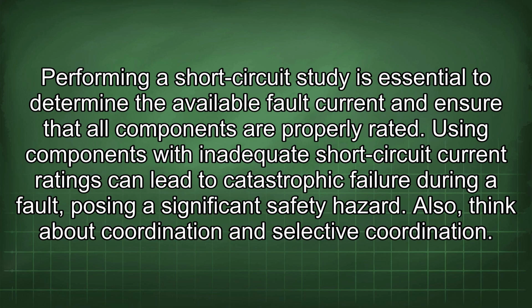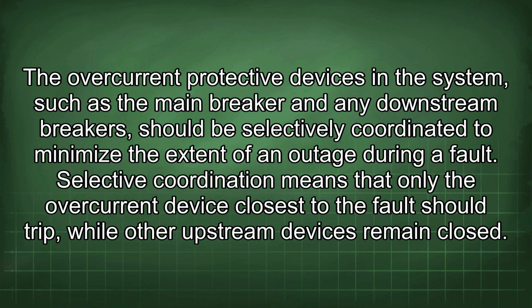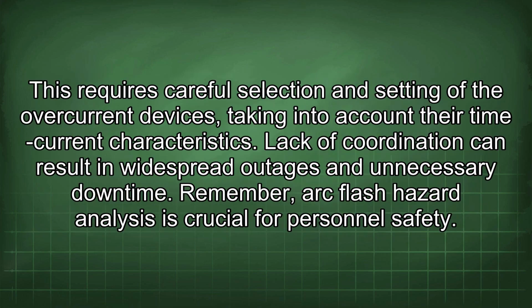safety hazard. Also, think about coordination and selective coordination. The overcurrent protective devices in the system, such as the main breaker and any downstream breakers, should be selectively coordinated to minimize the extent of an outage during a fault. Selective coordination means that only the overcurrent device closest to the fault should trip, while other upstream devices remain closed. This requires careful selection and setting of the overcurrent devices, taking into account their time current characteristics. Lack of coordination can result in widespread outages and unnecessary downtime.